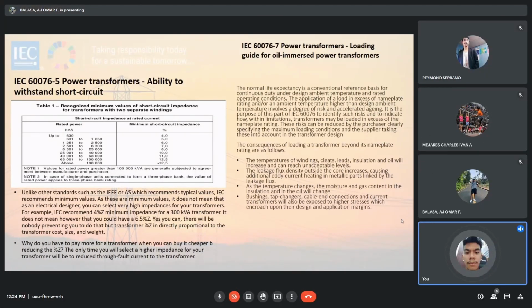So, dito naman sa IEC 60076-5, Power Transformers, ability to withstand short circuit. So, dito makikita natin sa table is yung mga computed standard nung para sa short circuit ng mga power transformers. Sabi dito is, unlike other standards such as IEEE or AS, which recommends typical values, IEC recommends minimum values. As these are minimum values, it does not mean that as an electrical designer, you can select very high impedances for your transformers. Example is IEC recommends 4% of minimum impedance for 300 kVA transformers. It does not mean, however, you could have 6.5%.